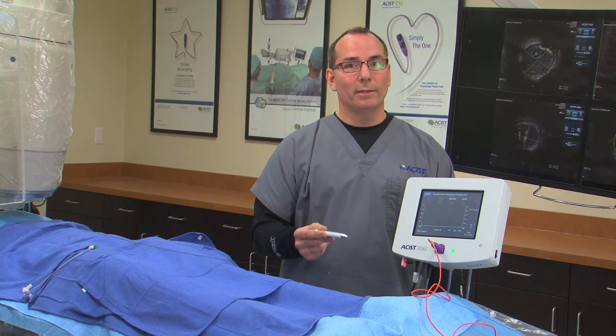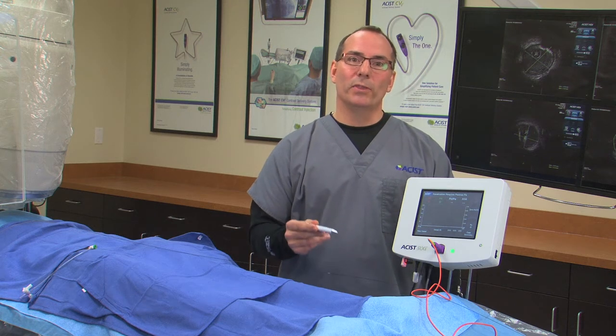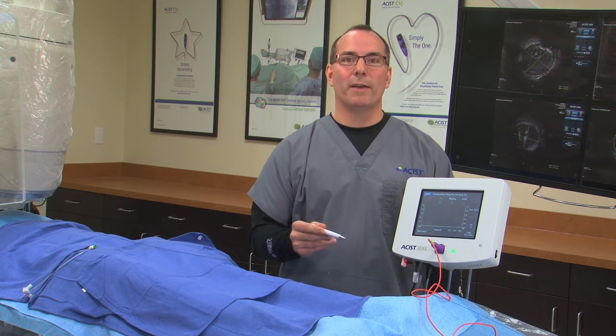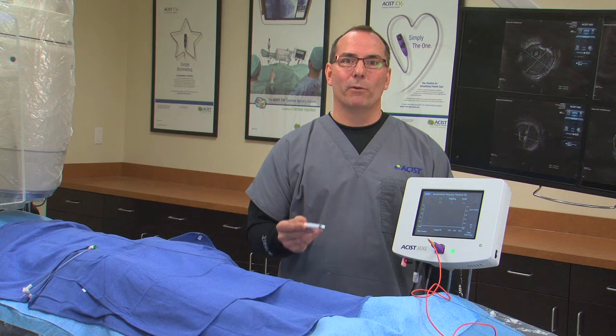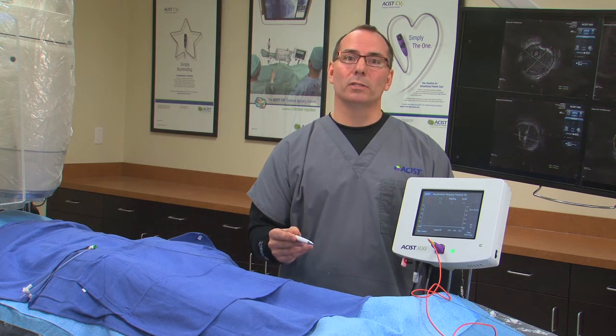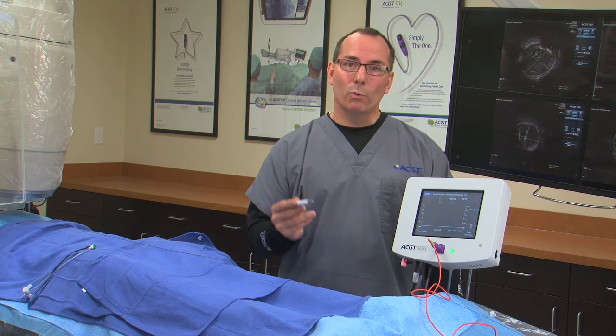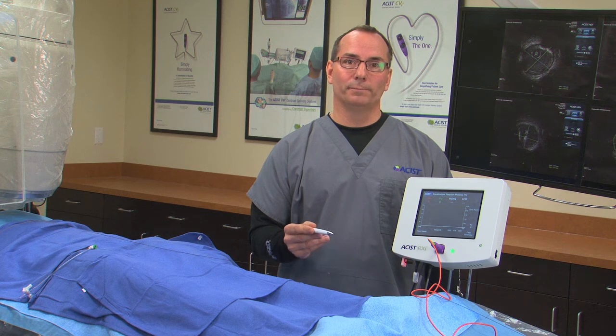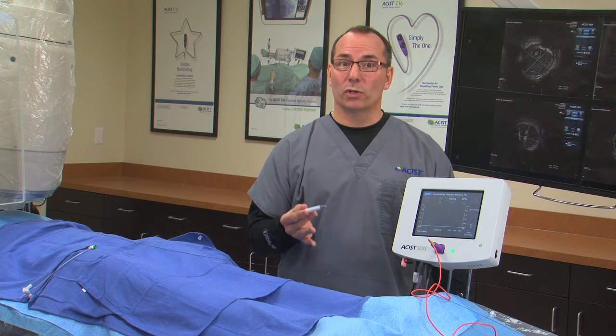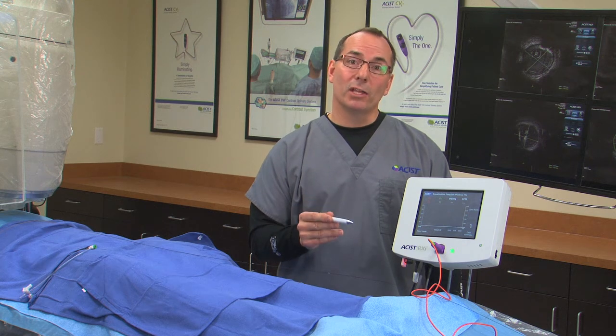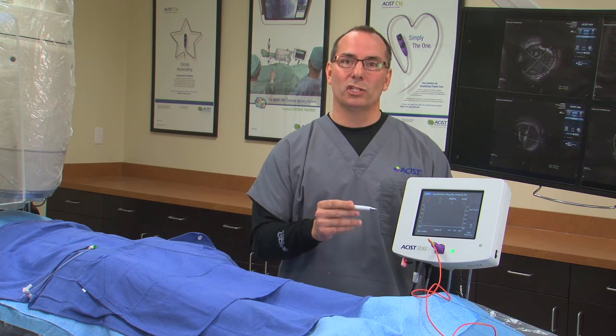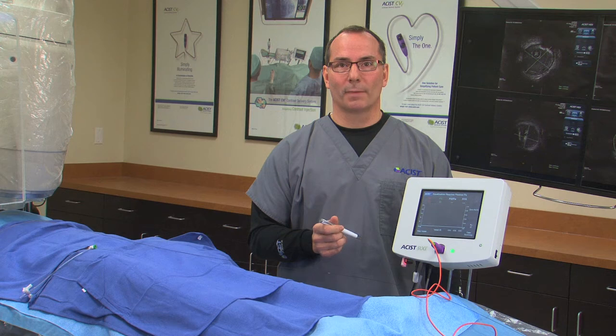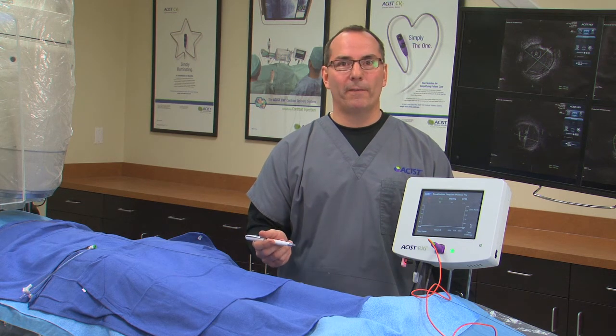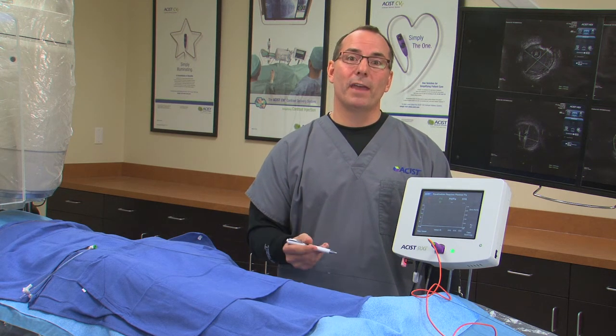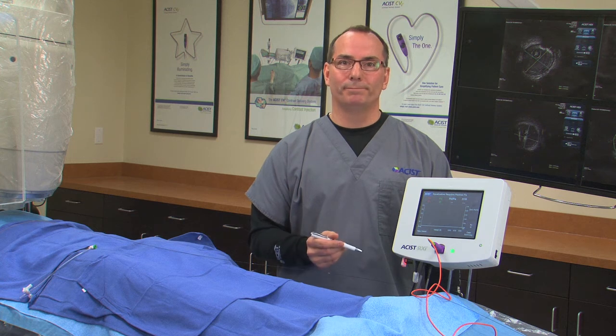Now PV allows the user to input a central venous pressure into the FFR calculation. For an accurate FFR, it's important to remove the resistance to blood flow. A high venous pressure increases resistance to blood flow, therefore a PV value should be used in the calculation of FFR. The RXi is the only FFR system in which the PV value can be easily input.